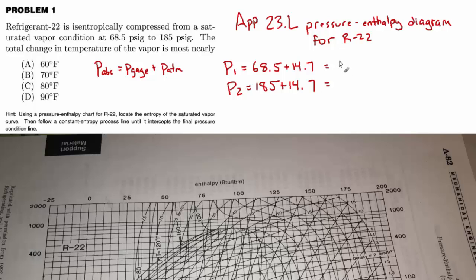And P2 equals 185 plus 14.7. P1 is 83.2 PSIA. And P2 is 199.7 PSIA. And to identify any point on a refrigeration diagram, we need to know two things about that state. So for state one, we know the pressure. And the other fact that we have is that it's a saturated vapor. So we're going to find it right on the outside of this curve, on the right side where the saturated vapor is.